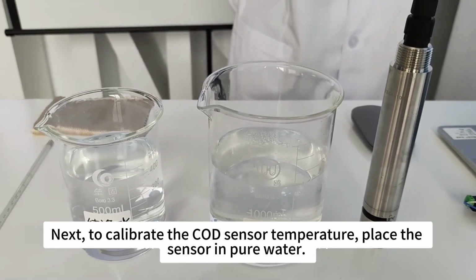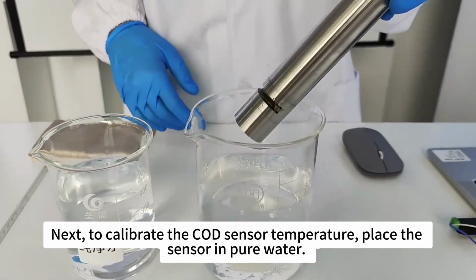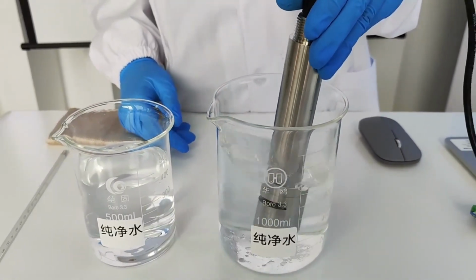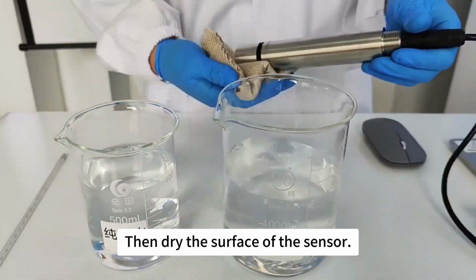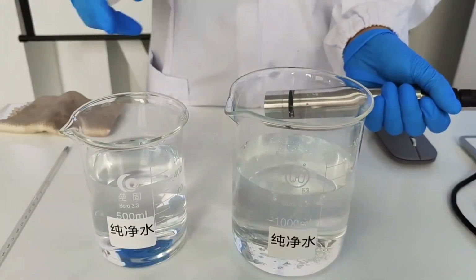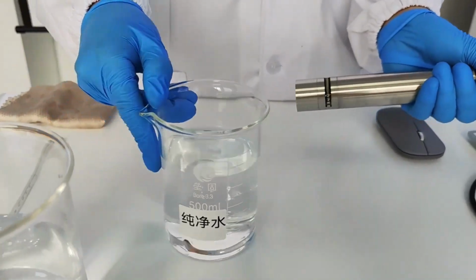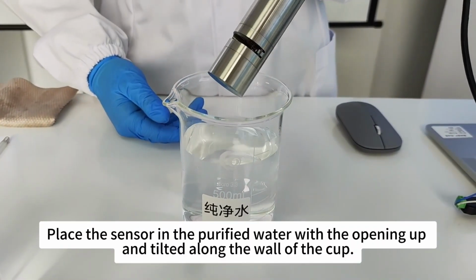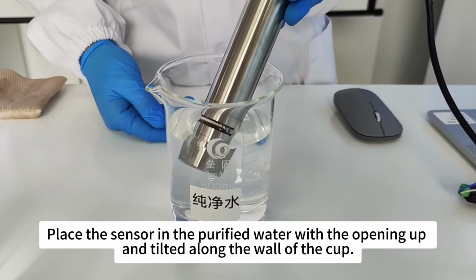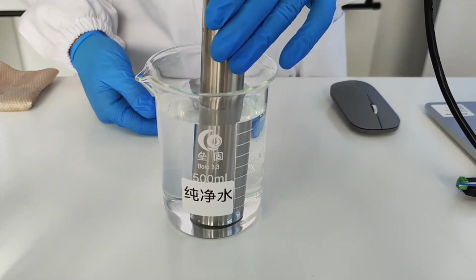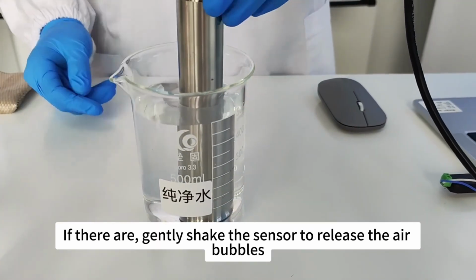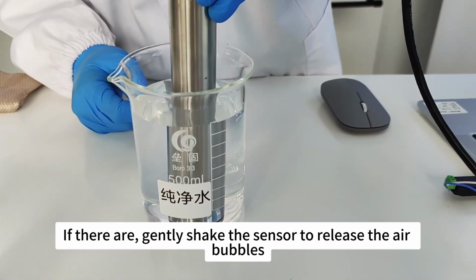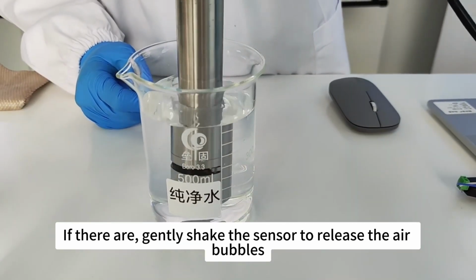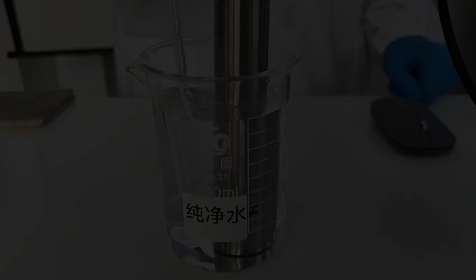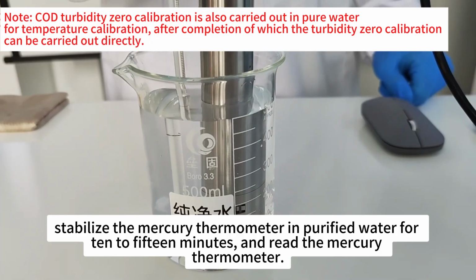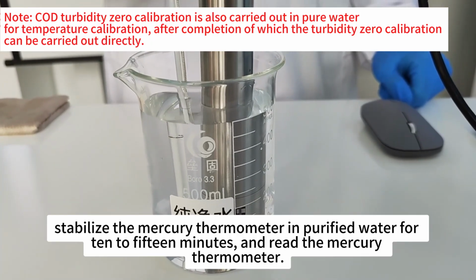Next, to calibrate the COD sensor temperature, place the sensor in pure water. Then dry the surface of the sensor. Place the sensor in the purified water with the opening up and tilted along the wall of the cup. Look for visible bubbles on the open side of the surface. If there are, gently shake the sensor to release the air bubbles and stabilize the mercury thermometer in purified water for 10 to 15 minutes. Read the mercury thermometer.